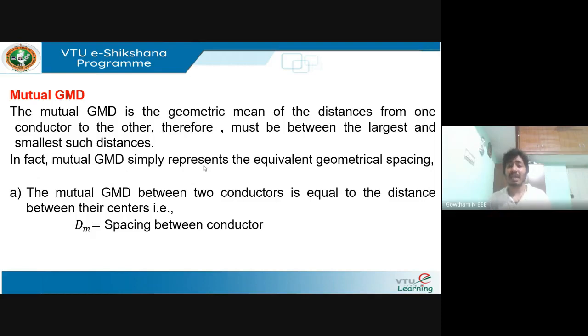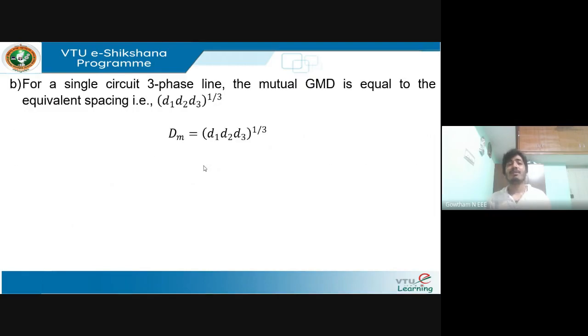The mutual GMD represents the equivalent geometrical spacing between conductors. Its value lies between the largest and smallest distances. The mutual GMD between two conductors equals the distance between their centers. For a single circuit three-phase line, the equivalent mutual GMD is (D1 × D2 × D3)^(1/3), where D1, D2, D3 are the inter-conductor spacings.